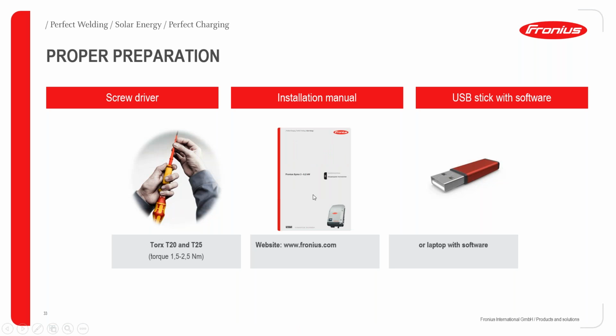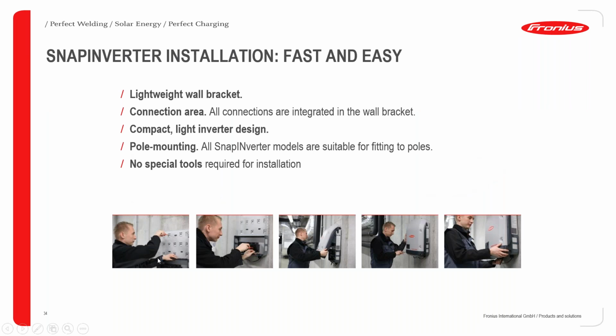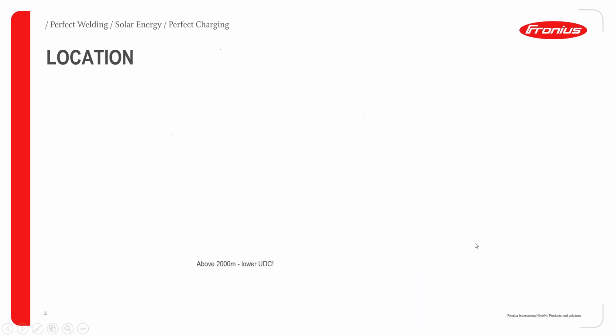So basically we'll now go through the installation process of our inverters. It doesn't really require much. All you need, in some cases, is just a screwdriver, your installation manual, and of course your USB stick in case you have to do some software updates or upgrades. Good. So first, install the wall mount bracket, carry out the DC and AC connections, snap in your inverter, screw the inverter onto the wall mount bracket, and then turn on the DC switch, and you're done with the installation. It's as easy as that.